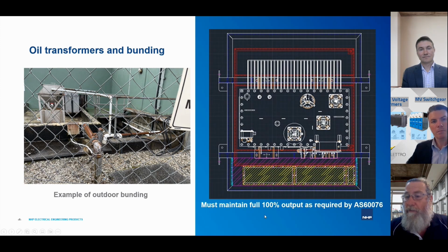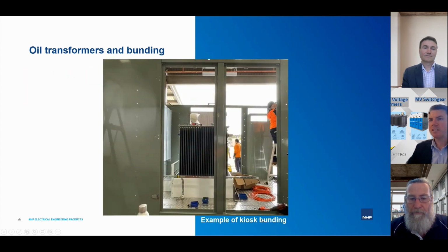I guess they could have just simply got a standard oil-filled transformer and used the same bunding, but they've been quite progressive in their view, and they have now got that standard outdoor oil-filled transformer sitting in a bunding inside an enclosure. Yep, excellent. So that's an outdoor approach.